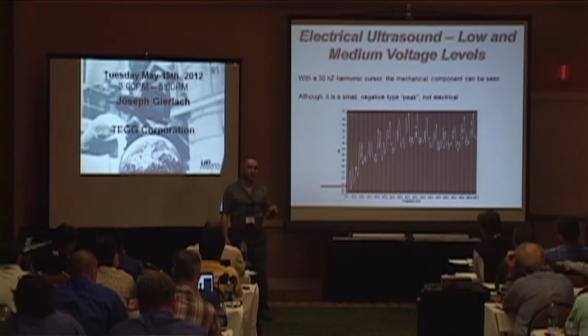Even defining it a little more - there's a slight 30 hertz peak on the bottom of this, which is unusual. I'm used to seeing them on top. But what do we know about a 30 hertz frequency on a 60 hertz system? It could be vibration, but it's not electrical - it would be mechanical in nature. So that definitely raised an eyebrow, and it started us down a different road of it could be this, it could be that.